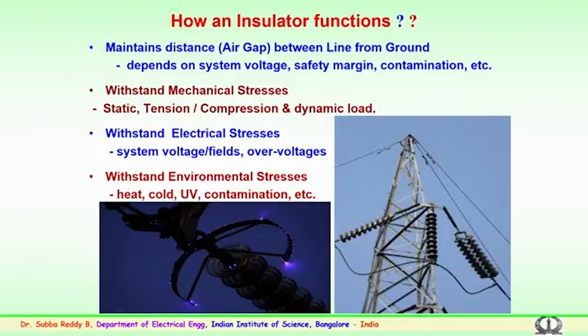So, we looked into how the insulator functions, and we saw that it is important both mechanically and electrically. Particularly, it maintains the distance, that is the air gap, between the line and the ground. For the voltage seen on the conductor, the minimum clearances have to be maintained from the ground, to see that under normal conditions, or during fog, rain or polluted conditions, flashover does not happen from the line to the ground. This again depends on the system voltage, the safety margin employed for the design, the contamination levels at the area where the transmission tower exists, and so on and so forth.